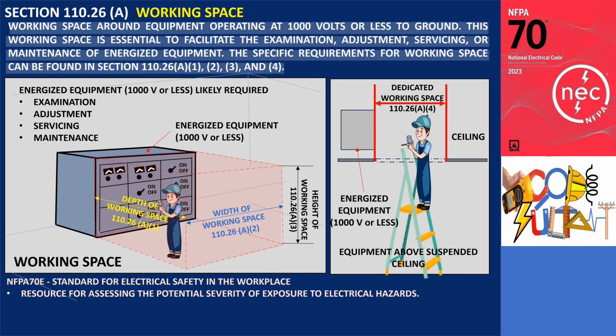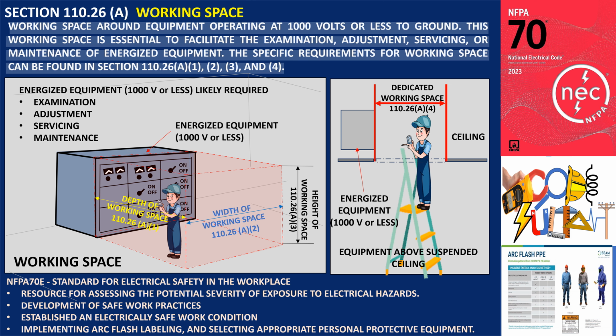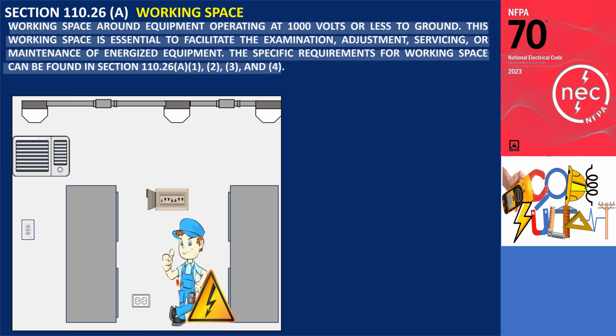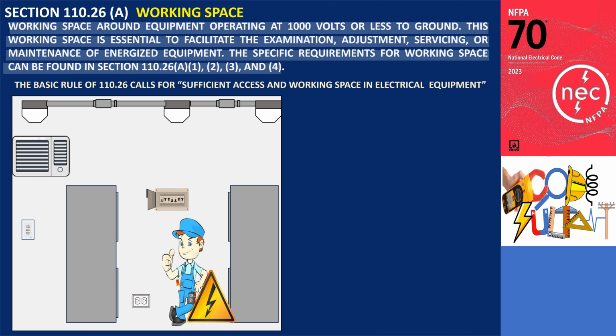severity of exposure to electrical hazards. It also assists in the development of safe work practices, which include establishing an electrically safe work condition, implementing arc flash labeling, and selecting appropriate personal protective equipment. The basic rule of 110.26 calls for sufficient access and working space to be provided in all cases to permit the ready and safe operation and maintenance of electrical equipment.